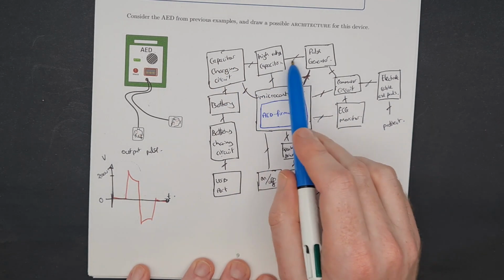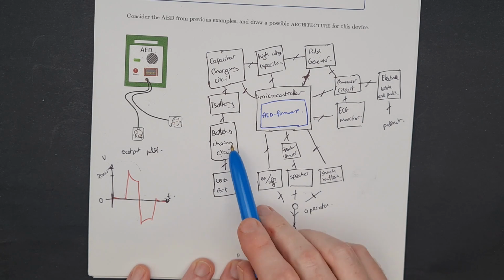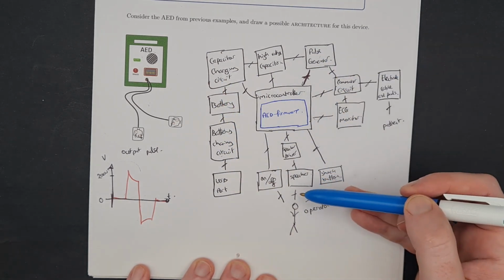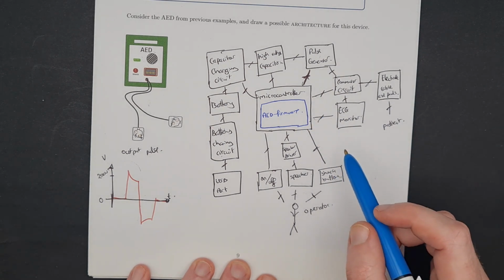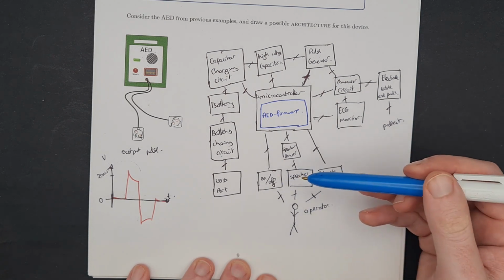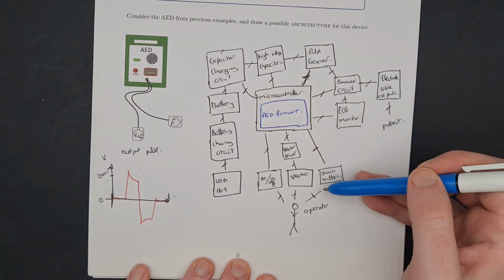Now, these are all items, okay, which is helpful because then in our documentation, I can make a detailed description of each below this figure, and it can be really clear to people who are auditing us how the device is designed. And as well as that, we want a clear understanding of how the device is decomposed to identify certain risks.